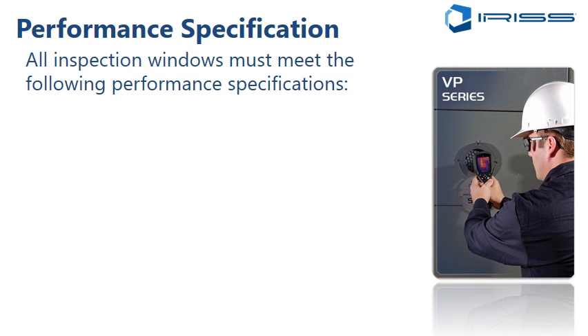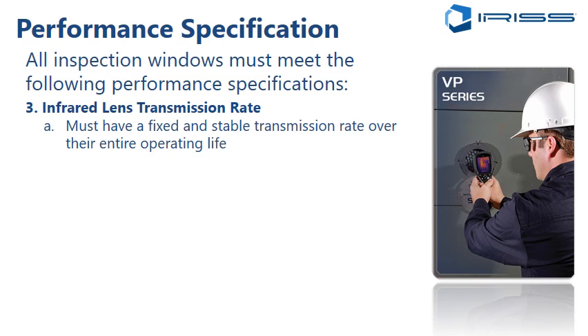Now, all inspection windows should also meet the infrared lens transmission rate. I spoke briefly about infrared transmission. It's super important. Your lens material must have a fixed and stable transmission rate over its entire operating life. So you don't want to use hygroscopic materials, because they will change over the term of their life. You need something that stays fixed and stable. And if it's fixed and stable, you can use it today, you can use it in 20 years, the transmission rates are going to be the same.